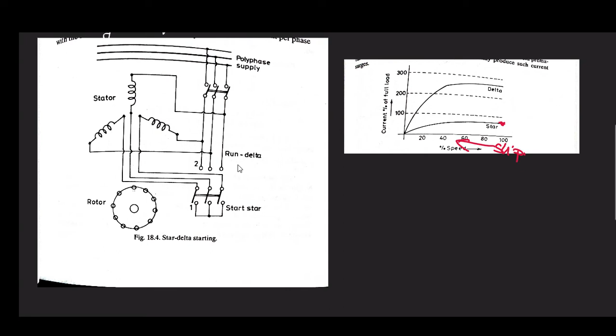Now, in case of starting of a wound rotor induction machine, all these starting methods of squirrel cage induction motor are applicable to wound rotor. But in addition, there is a flexibility the wound rotor induction machine offers. You can add an additional rotor resistance, because the wound rotor circuit is accessible from outside, it is available to the external operator. So we can change the setting of the wound rotor machine.